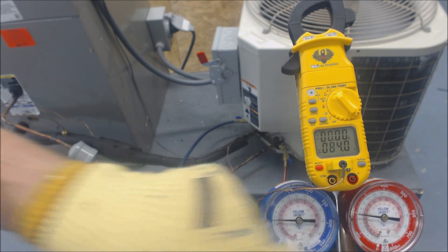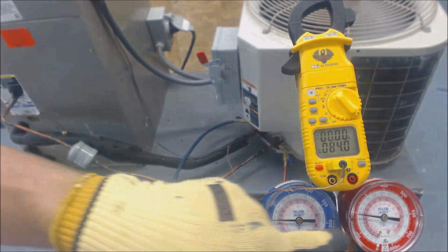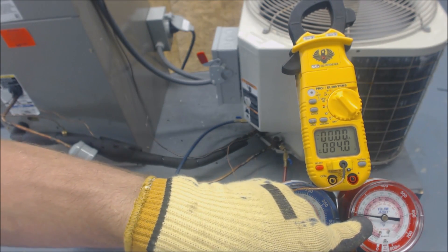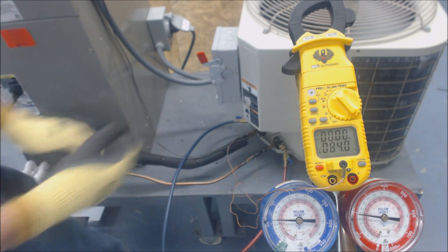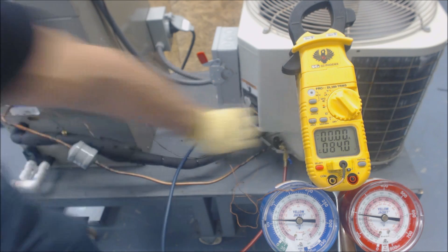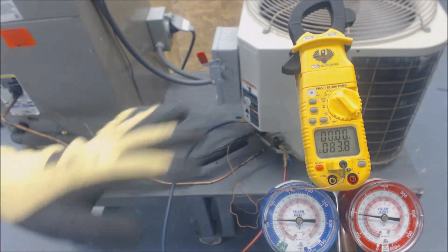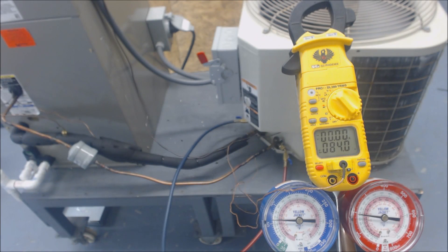For R22, you bring the dial in from 192 PSI and you follow it over to the green saturated temperature. The saturated temperature is the temperature right here in the middle of the condenser coil. We've got 99 minus 84, so that's 15 degrees of subcooling. That's telling us we have the correct charge.